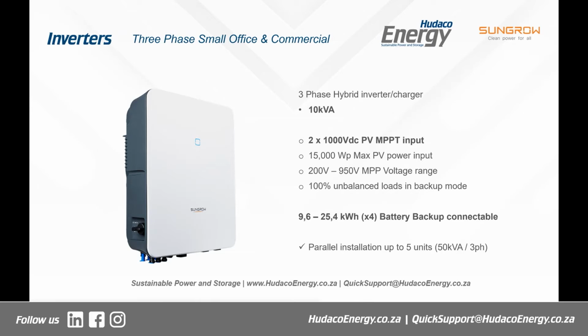The answer is no. For each unit, you've got 3.3 kVA per phase, and they can operate completely unbalanced. What I mean by that is you could have one operating at 3, you could have one operating at 1.5, and you could have a third phase operating at 0 load at all, right? If you've got 3 of them in parallel, you would have effectively 10 kVA per phase that you could run totally unbalanced. Okay, really, really, really neat piece of kit. Next, please.